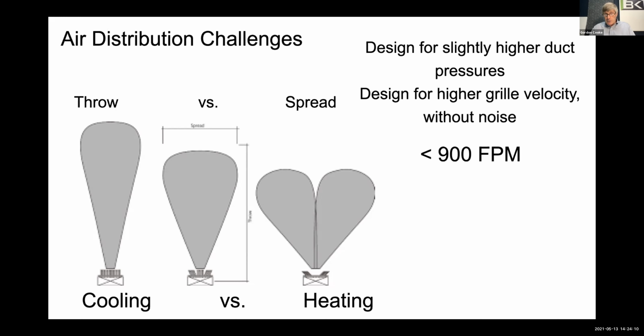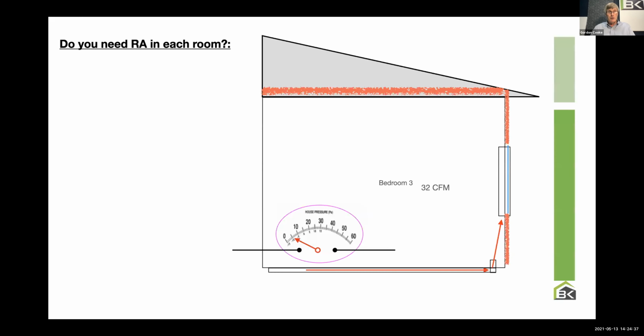So lower is better, but you can design for more. But the key is to decide whether I want throw or spread in any particular application. And rooms on the second floor, well, frankly, in cooling mode, you really would like throw versus spread. You like to get that cooling up. Now, are there grills that can do both? And the answer is yes. You can get adjustable grills that can spread in the winter and throw in the summer. You can get adjustable grills.